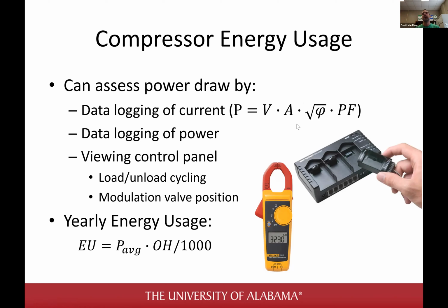So if you want to know the power being drawn by the compressor: voltage, often 480, times the amperage you're measuring, times the square root of the phase (3), times some power factor, PF. I won't go too deep into this, but power factor is the ratio of real to apparent power. If you don't know what that means, just let power factor be 0.8. If you do know, check your motor specifics, but it'll be around 0.8 anyway, so just leave it at 0.8 and let's continue.